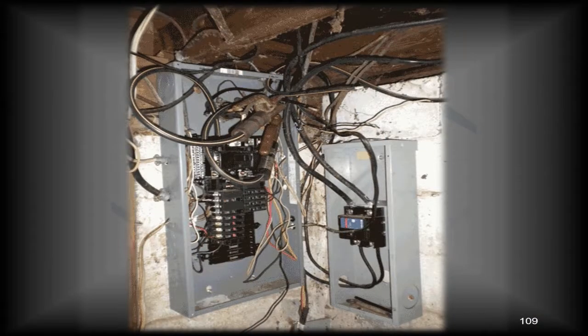Now, obviously, things have certainly gone sideways here. We've got some service coming in here, and it is all over the place. It looks like potentially there's some mold on the wall, maybe some mildew on the wall, and so we've got some moisture down there. Things are rusted. We're below level, so we've got all kinds of things going on in this picture here that make the installation probably not comply.